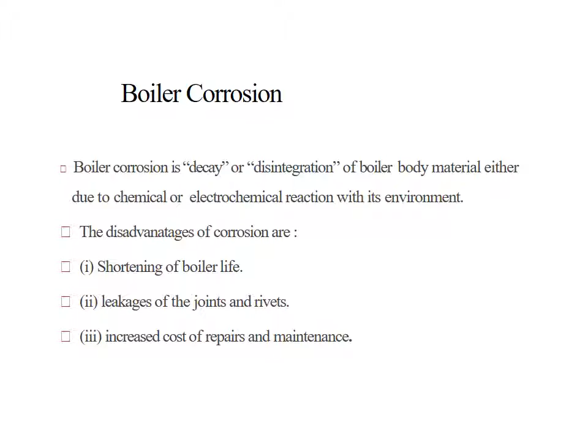Corrosion in a boiler is due to the following reasons. Various reasons cause corrosion in the boiler. The first reason is dissolved oxygen. This is the most usual corrosion causing factor of the boiler. In the boiler, oxygen is introduced through the raw water supply. Water usually contains about 8 ppm of dissolved oxygen at room temperature.